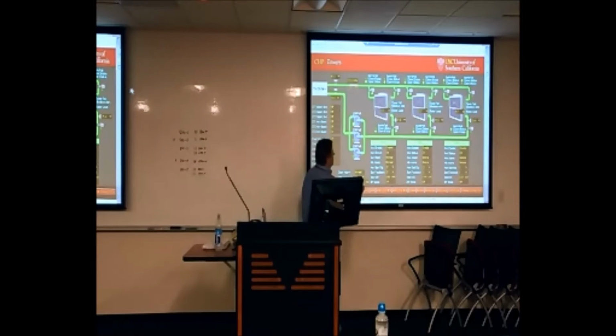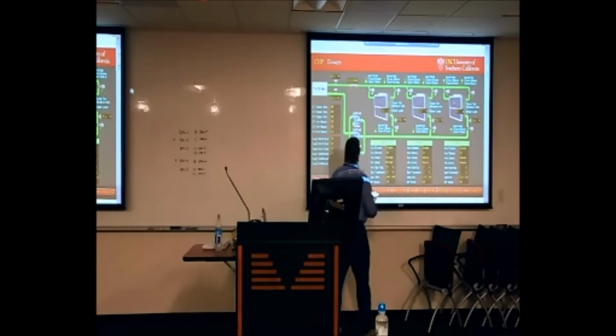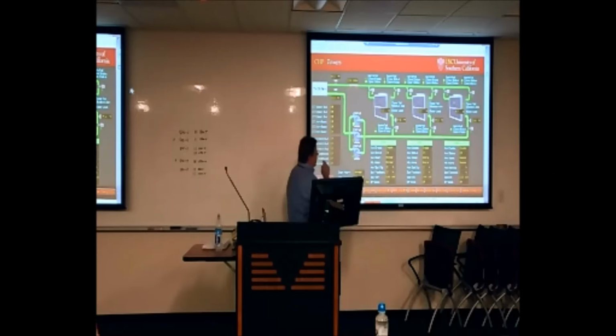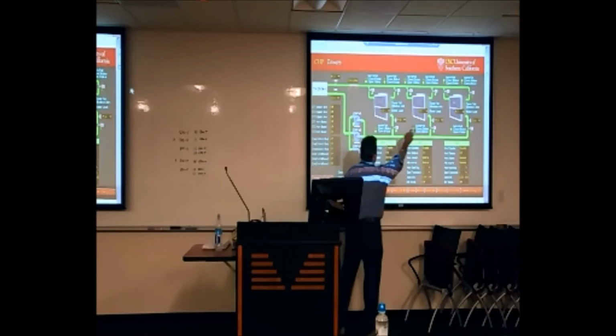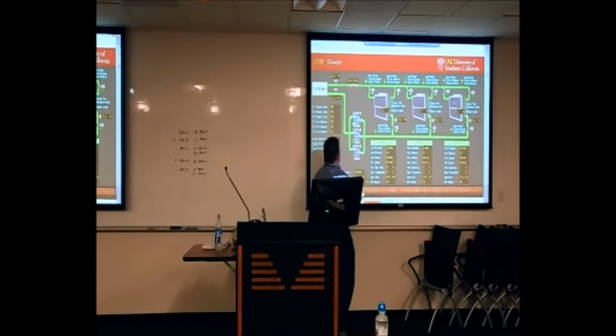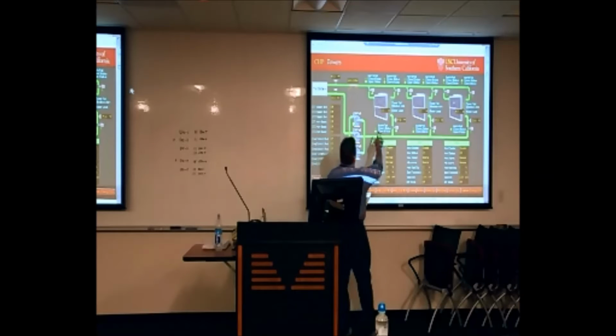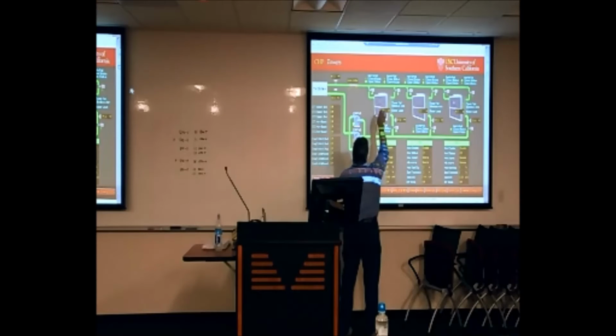The old tower system used to have 3 cooling towers, but it only had 2 pumps, and it ran a slightly different sequence of operation. This is basically the old graphic, just being modified now to represent the new points. So this is the new cooling tower project. We've got 3 cooling towers in the yard, and now we've got 3 pumps. And as a quick overview, we didn't have a walk this morning, but each cooling tower has 2 entering valves, one on each side of the tower, so it's a bray valve.